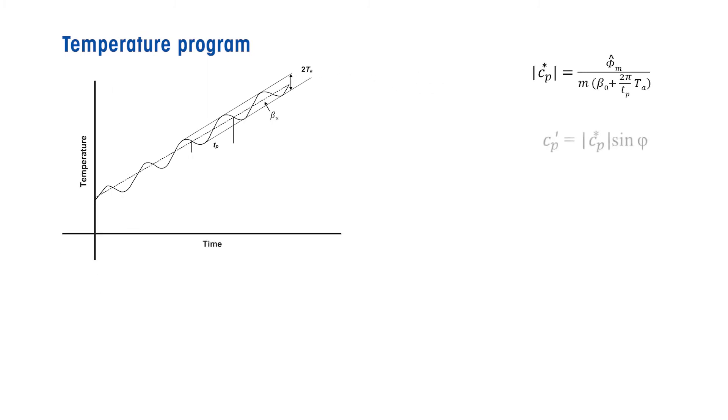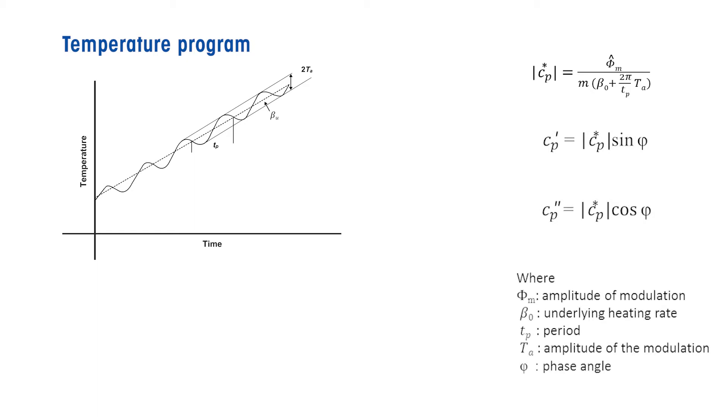Continuous averaging of the heat flow over one cycle yields the total heat flow generated by the underlying heating rate. The total heat flow corresponds to the measured curve in a conventional DSC experiment. The reversing heat flow is determined from the amplitude of the modulated heat flow and the modulated heating rate. The difference between the total heat flow and the reversing heat flow gives the non-reversing heat flow.